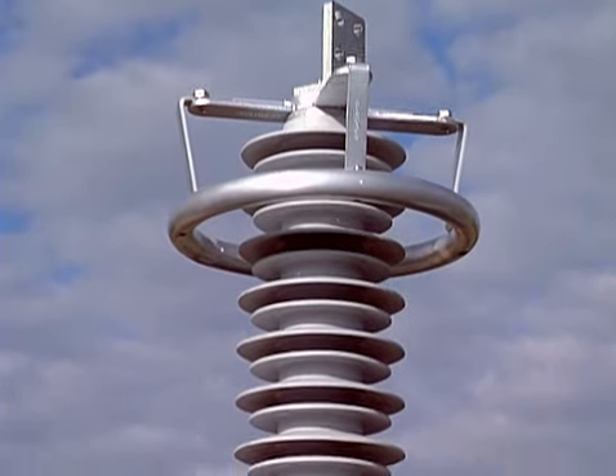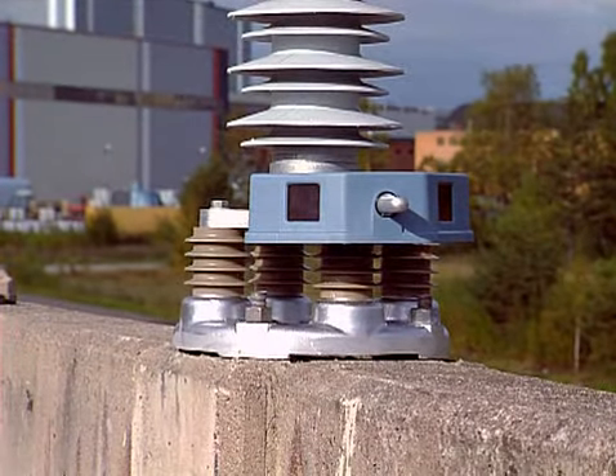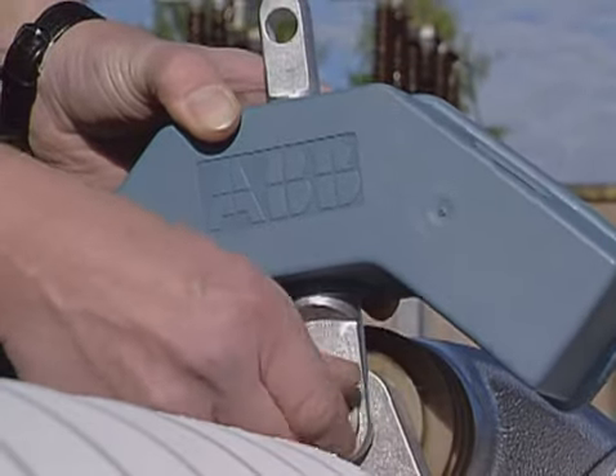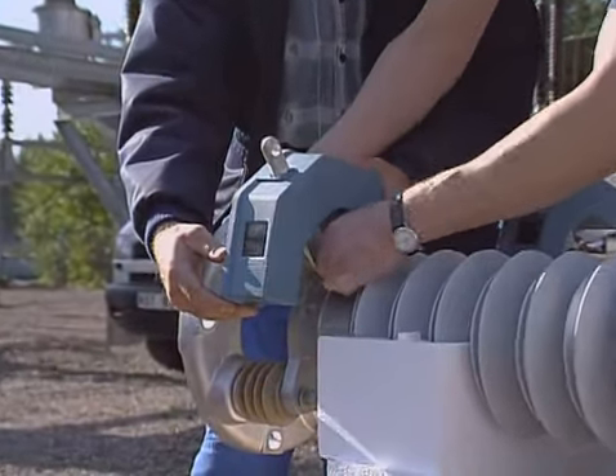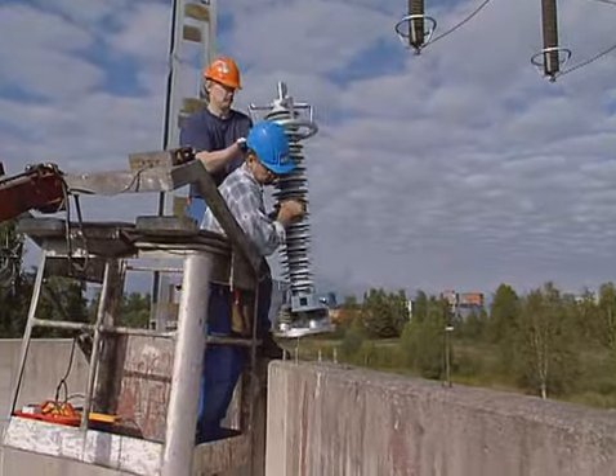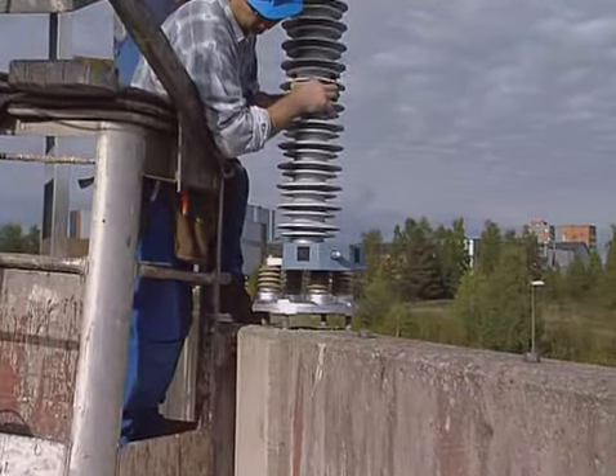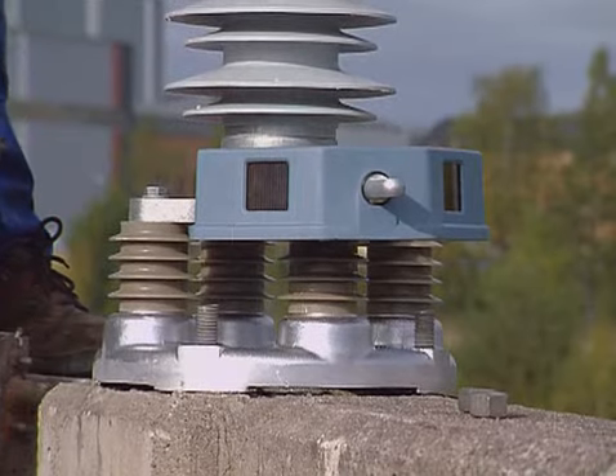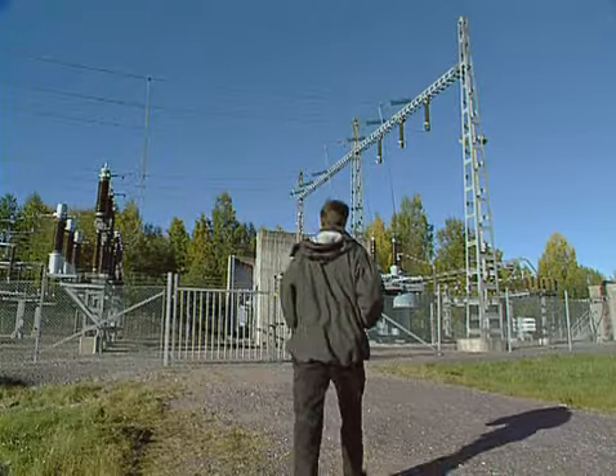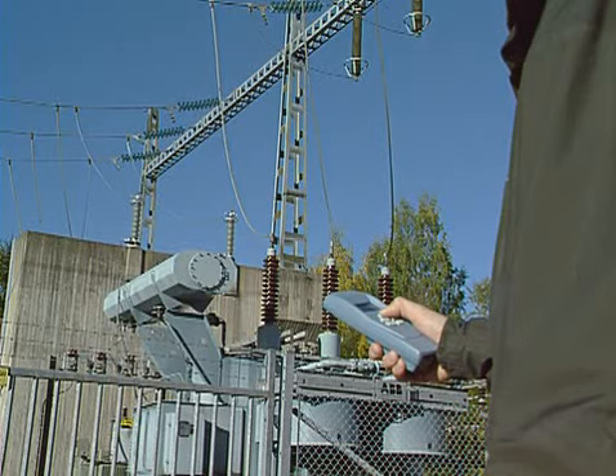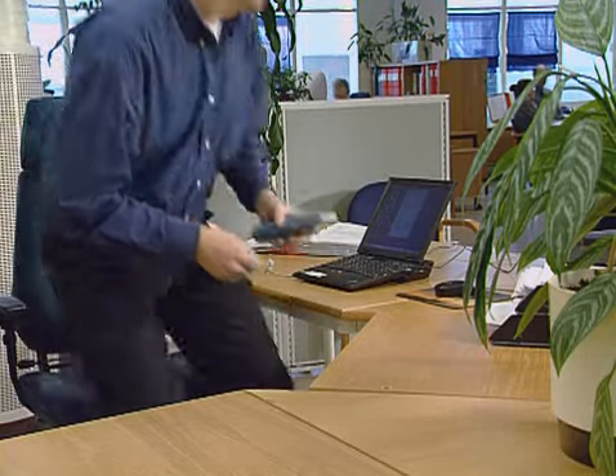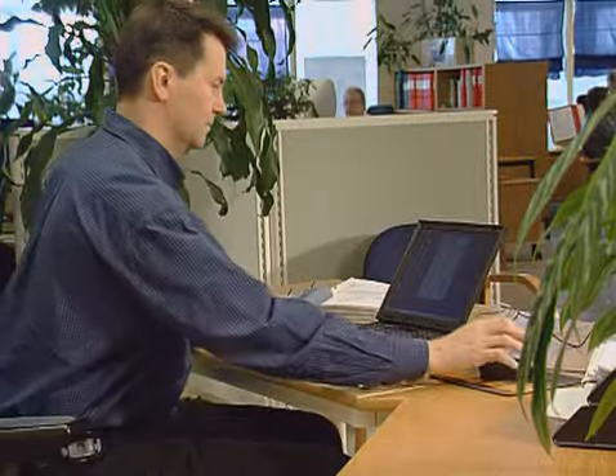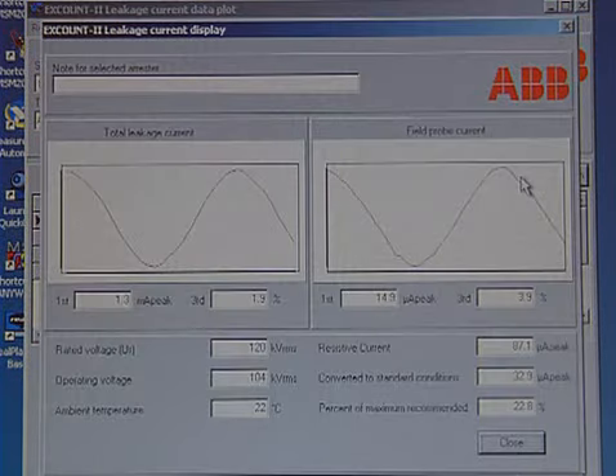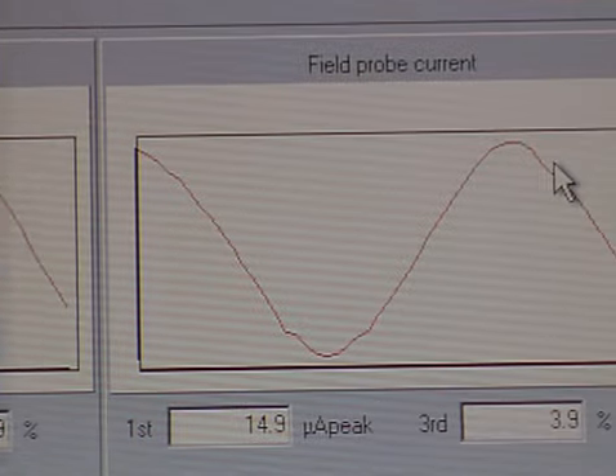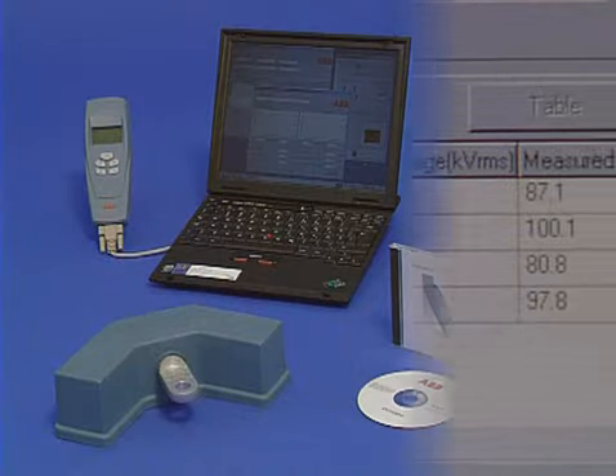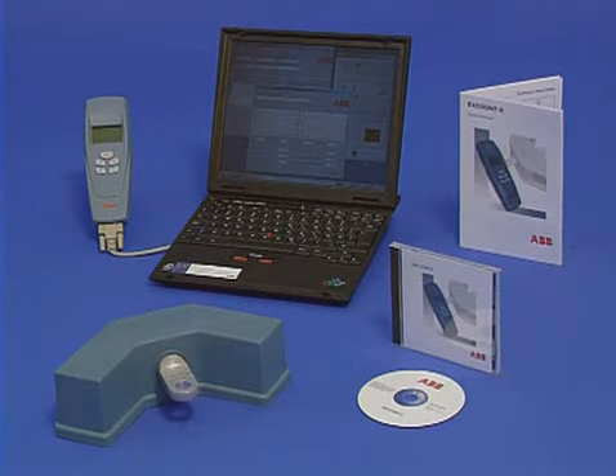For new installations, it is possible to install ABB's new advanced monitoring system X-Count-2 for continual status monitoring. In addition to its surge counter function, X-Count-2 also registers discharge amplitude, date, and time, as well as having the option of measuring the total leakage current. Measurement results can be stored in the sensor unit, and the information can easily be retrieved and read using a wireless handheld unit. Analysis can be done on-site or via a PC for statistical processing. There is also a version of X-Count-2 that measures resistive current, which is an indicator of the arrestor's condition. X-Count-2 is a superior alternative for continuous monitoring, as many customers have already discovered.